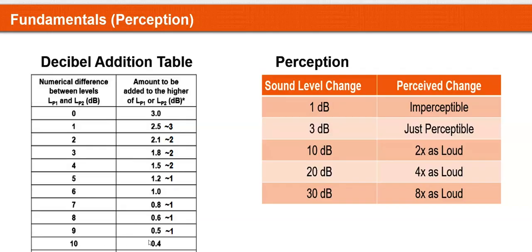In other words, even when you look at self-generated noise by other pieces of equipment, or at the added sound power levels of a single duct valve in the duct, as long as those sound power levels are 10 decibels lower than what's remaining in the system, you are not adding noise to the system. So remember, the number 10 is handy. If you have two fans at 70 decibels each, the resultant value is going to be 73.